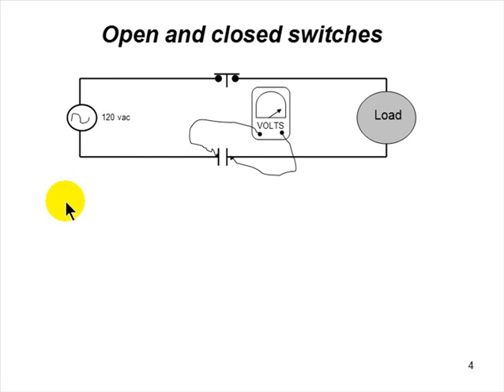Open and close switches. If I have a power source, a closed switch, and a continuity through a load, and this switch is open, what am I going to read here? I should read 120 volts. I should read the applied voltage. Because when you hook up your meter this way, it's the same as reading from here to one side of power and the other way through this load, through the switch, and back to the other side of power. It's the same as putting your meter on either side of the source or the plug in the wall or the receptacle in the wall.